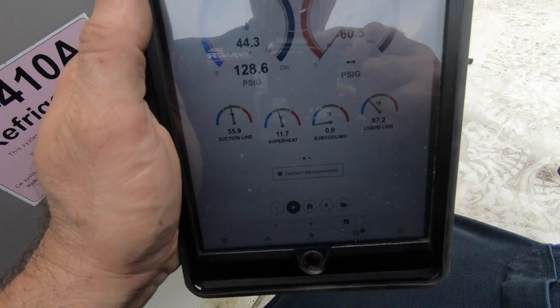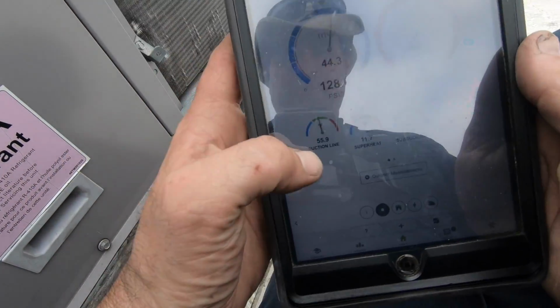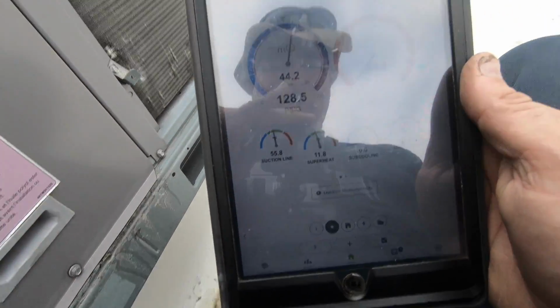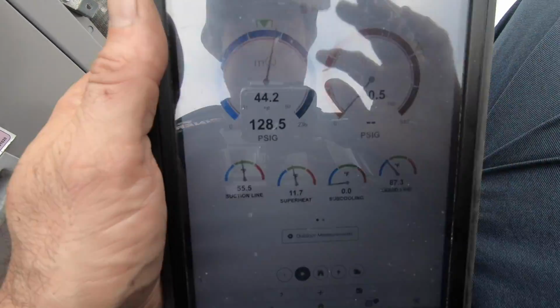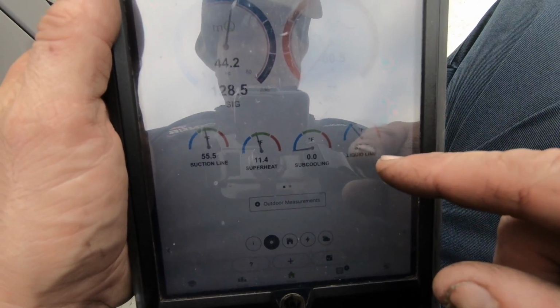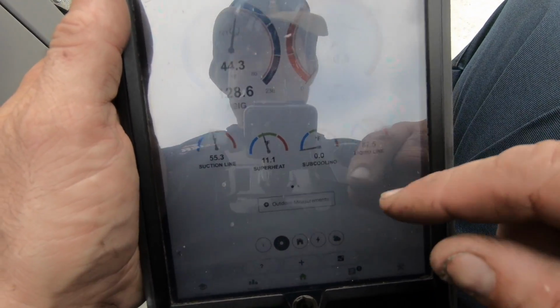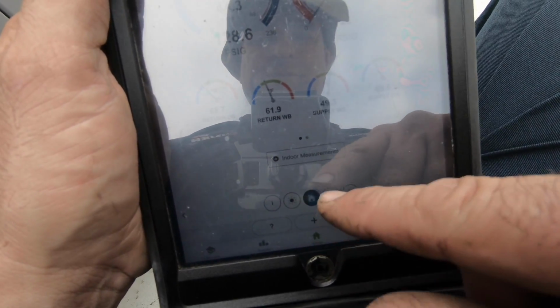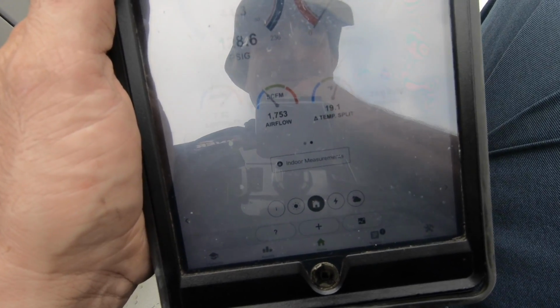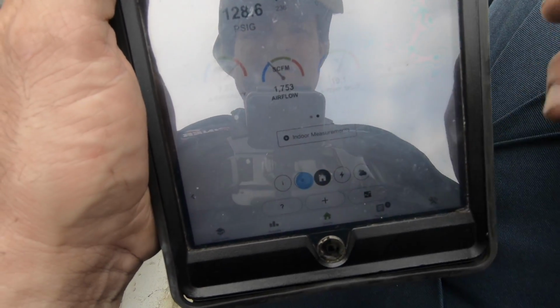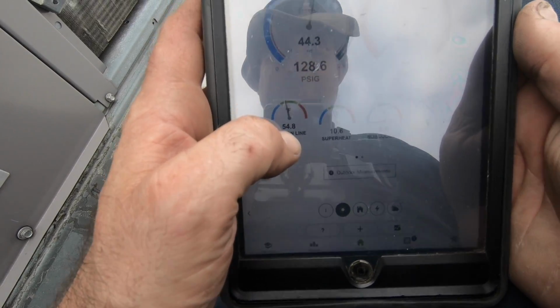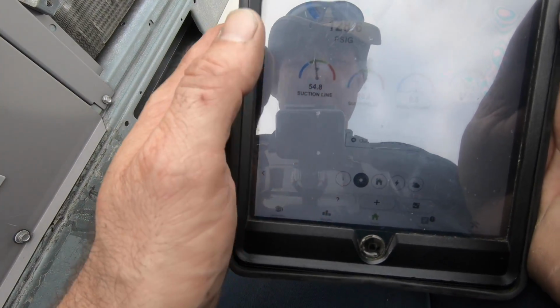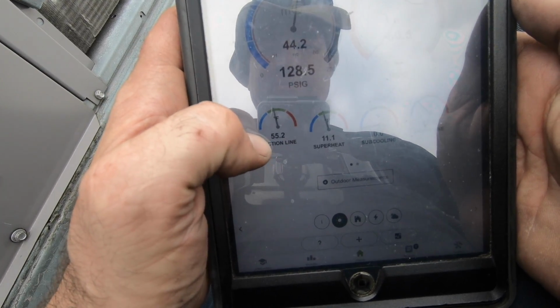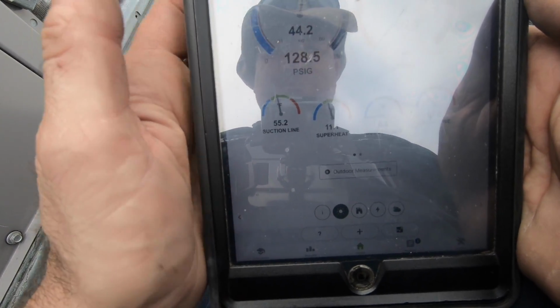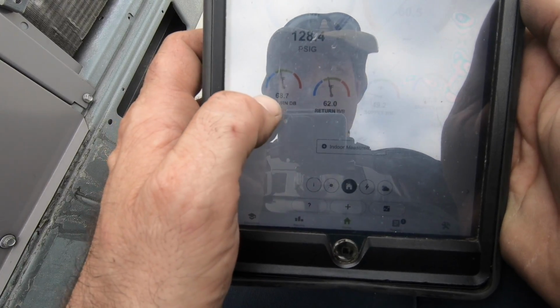Finishing off with 11 degrees of superheat, 55, almost 56 degrees suction line temp. That's pretty good right there. 87 liquid line, it's about almost 80 degrees now. Indoors, we have a 19-degree split. I'm happy with everything I'm seeing here. And this has been running for some time now. I just walked back over to it. 55 is my suction line, so I'm down to 48, where my indoor temp right now is about 68.